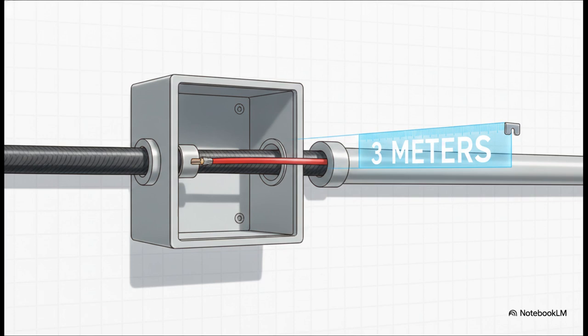Let's start with the 3-meter tap rule under Subrule 1b. You can actually decrease your wire size without putting a brand new breaker right at the tap, but only if you meet all of these specific conditions. 1. The smaller wire's ampacity has to handle the combined computed loads. 2. It absolutely cannot be over 3 meters long. 3. It can't extend beyond the panel or the control device it supplies. And 4. It's got to be enclosed in a non-ventilated raceway or armored cable. You miss even a single one of those? Yeah, you are definitely failing your inspection.